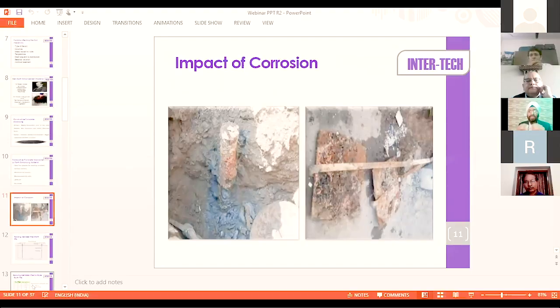Here's something I want to show. Why is longevity not there? Because there is only one reason for the failure of earth pits, and that reason is prevailing everywhere on this earth - it's corrosion. Due to corrosion only, earth pits fail. Most earth pits perform on account of moisture.